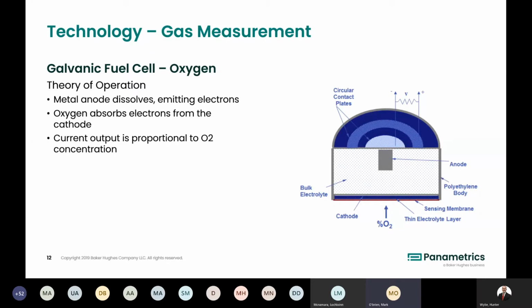The chemistry around it is a little bit complicated, so I'm not going to talk about that today. But just be aware that this cell will be changed out every 6 to 12 months or so. But it gives a very linear output depending on the oxygen concentration that's there. It can be ppm range or percent range. It again can be provided with a sample system. It can be used in general purpose areas or intrinsically safe requirement areas, and has a local display and a 4 to 20 milliamp output.